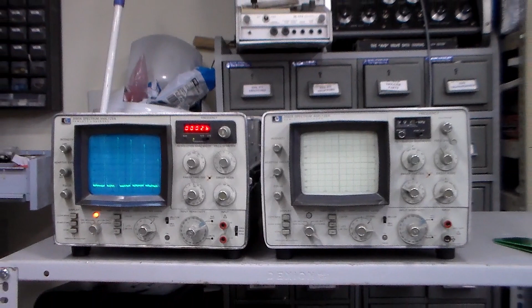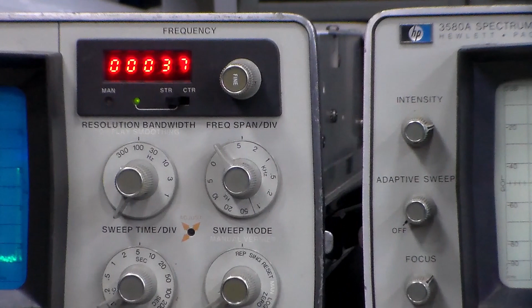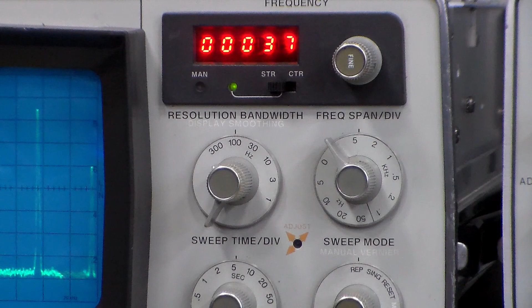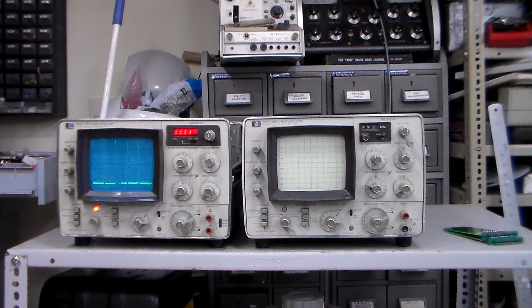Now the Mostek MK50399N counter chip has been replaced in the frequency display of this HP3580. You can see we've now got the display working beautifully, and the fault with the fourth digit has now been resolved. So both these spectrum analyzers are now ready to be fully recalibrated, and I shall go through the procedure straight out of the manual for that, and we should have two fully operational devices.